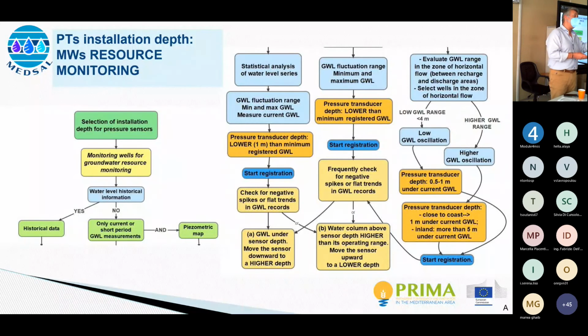You don't want to go to 0 to 150 meters simply because the resolution, the accuracy, is going to be reduced compared to a pressure transducer that has an operating range of, say, 0 to 10 meters. So be sure that you know exactly what you're dealing with, and based on that, you select. And always you need to go back and check on the data. Check whether you have correctly positioned your sensor in the well, and therefore it's not getting overpressured or outside the water.